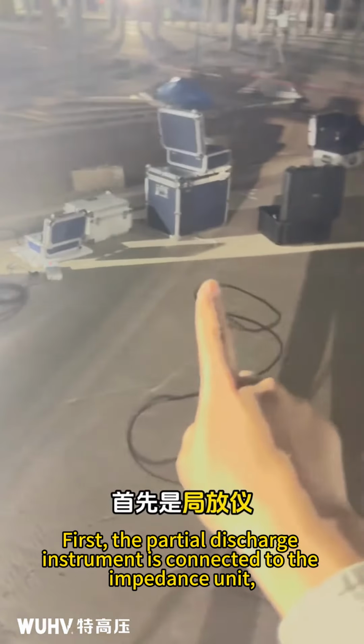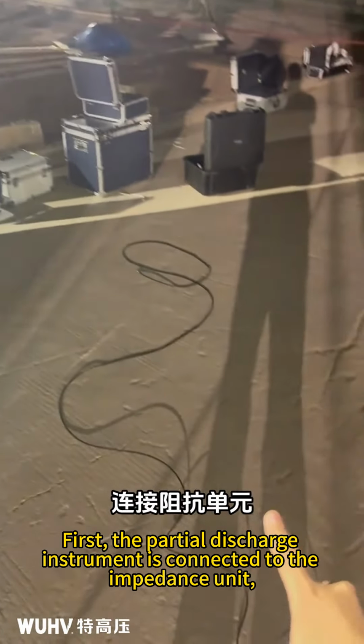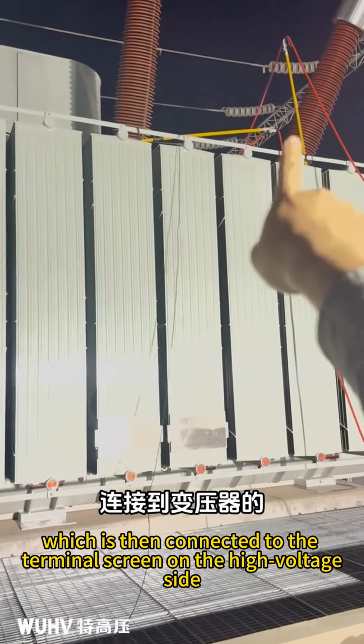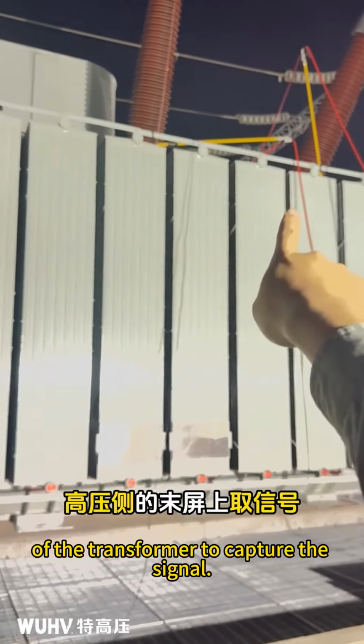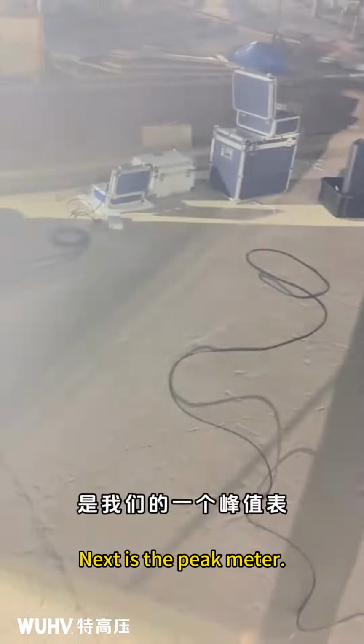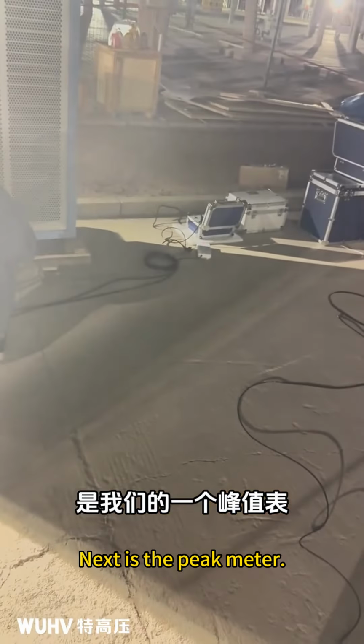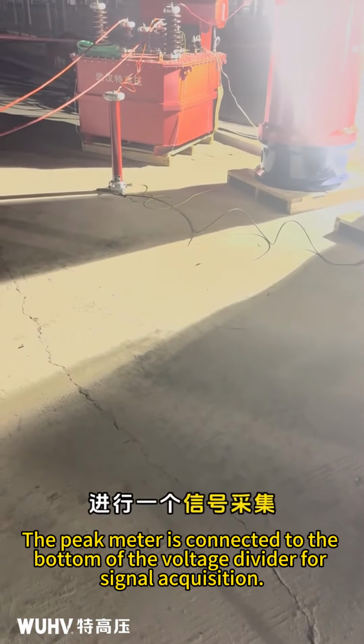First, the partial discharge instrument is connected to the impedance unit, which is then connected to the terminal screen on the high voltage side of the transformer to capture the signal. Next is the peak meter. The peak meter is connected to the bottom of the voltage divider for signal acquisition.